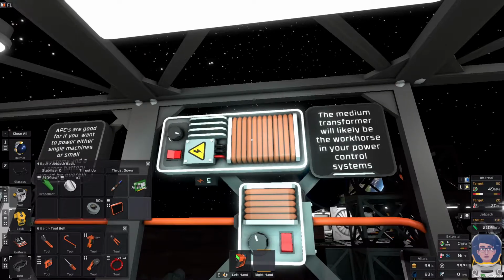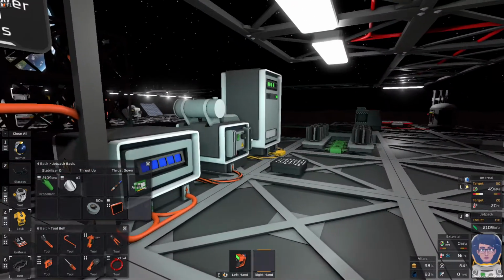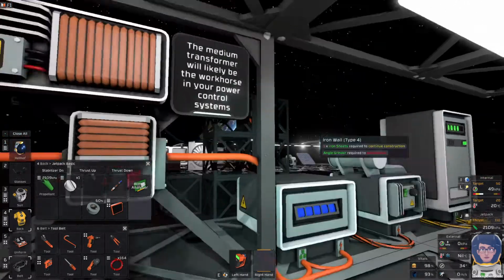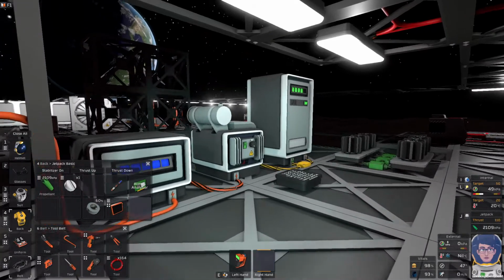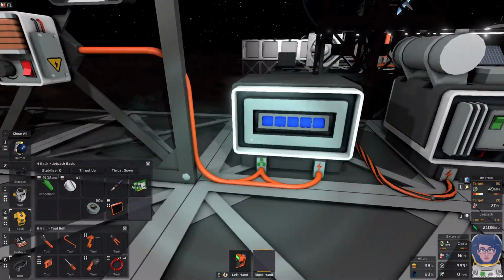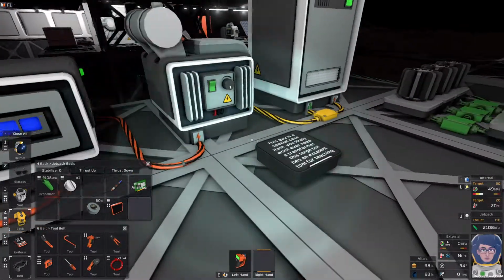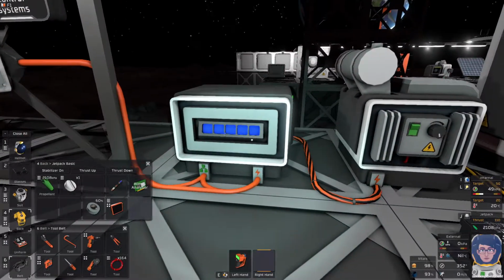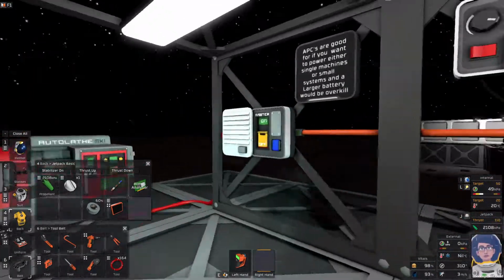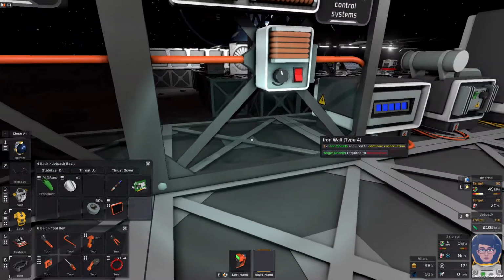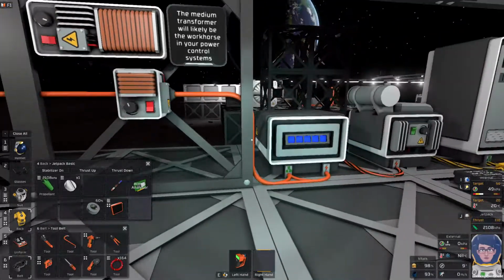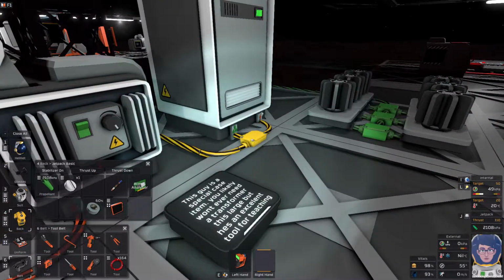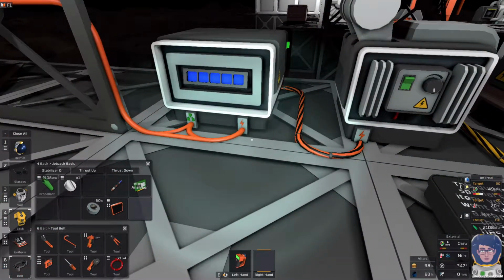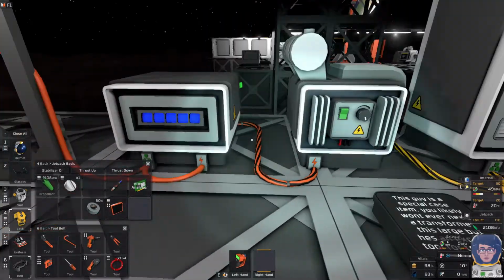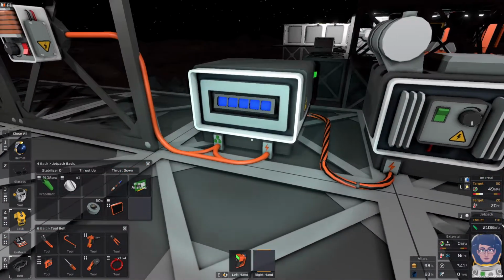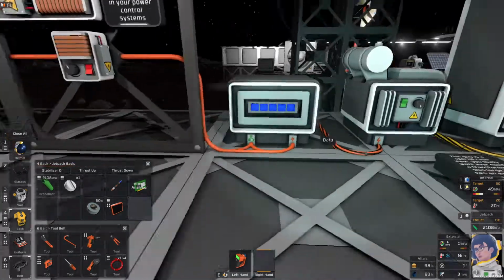Like I said, this medium one is likely going to be the workhorse for any large power protection, but you do have that option. So going over here, I have an orange cable, which is basically from a transformer to a sub-battery, be it a battery like this or an APC. It's basically just to differentiate between this, which comes off the main line, and anything coming off of a transformer, or like this here, a sub battery. It's just sub distribution.